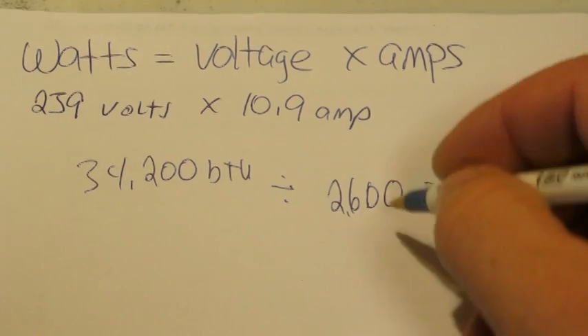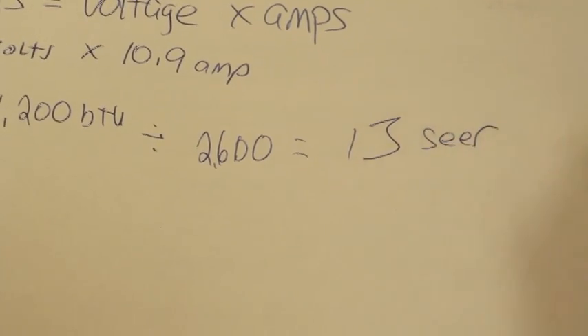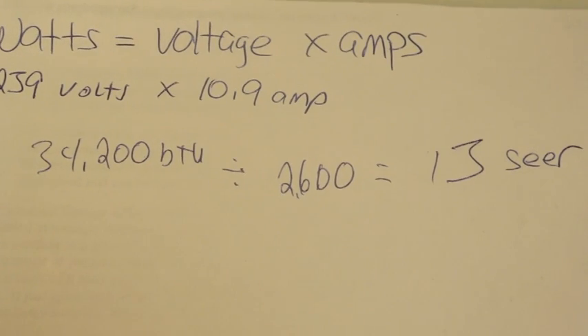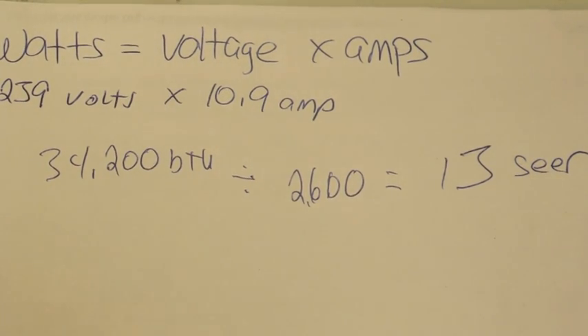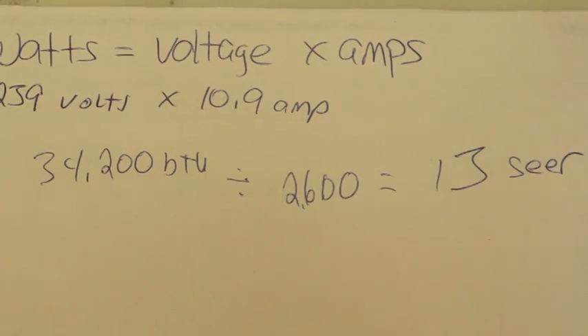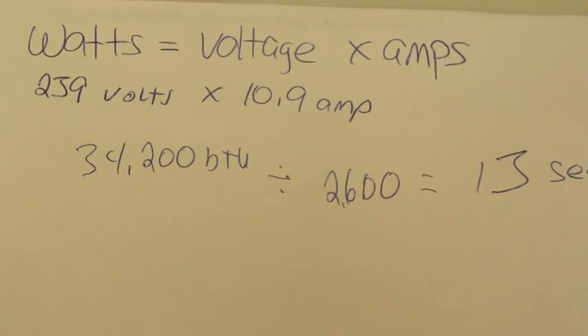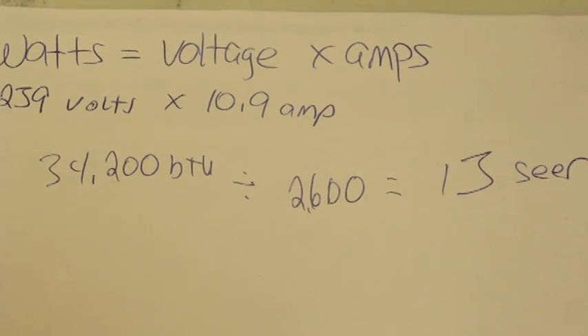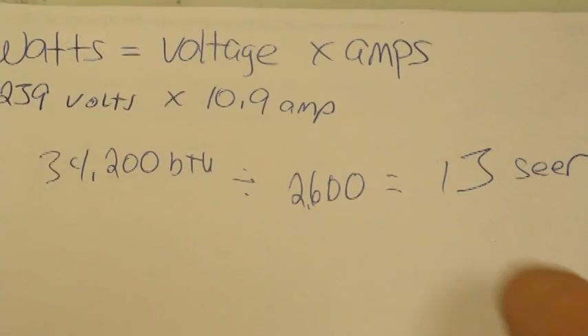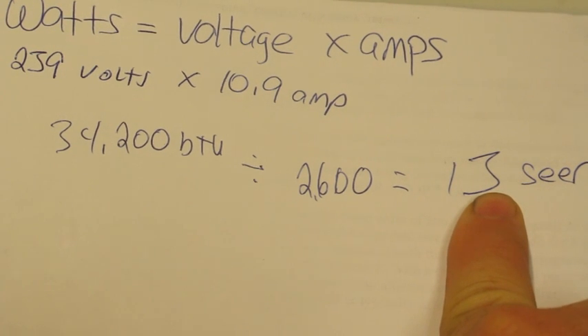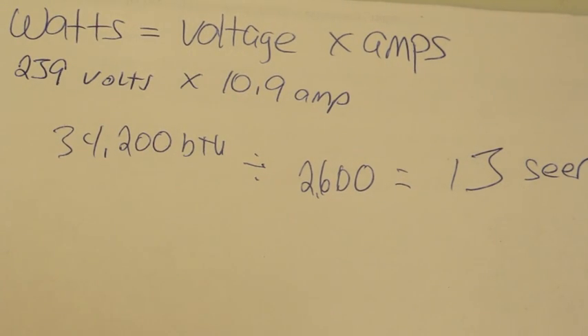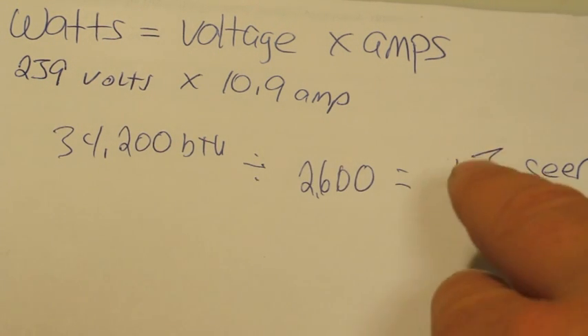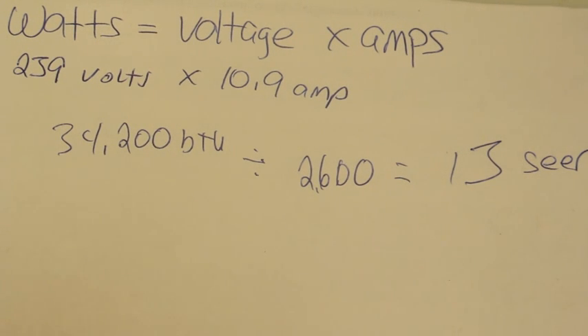Alright, the benefit of knowing this, if you're out doing your preventive maintenances, or you're doing a check and clean, and you've got a unit that's really dirty, or it's just not running properly, charge is wrong, whatever the case may be, if you just real quick take this measurement down and show them, listen, right now your air conditioner is running at this SEER rating, then you perform your maintenance, you clean it, you get the right charge and get everything working properly, then you retest this and say, okay, after your cleaning, everything that I've done, now we're up to 15 SEER, or whatever the case may be.